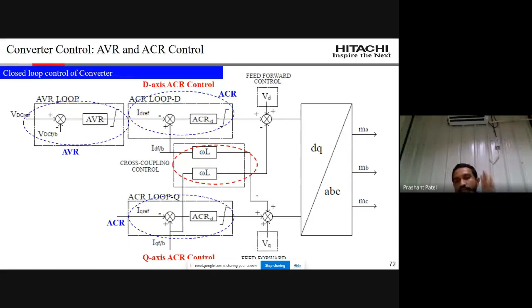But is this control sufficient to work in all scenarios? My answer is no, it's not possible. We have to think about extra features to add to this controller. Like with AVR and ACR, there is cross-coupling control, because we are working in the D channel and Q channel, and both channels should work independently. If changing something in the D channel affects the Q channel, that will ultimately affect your final control signal, the modulating signal, so it is not advisable. So we have to use cross-coupling control and feed-forward control.